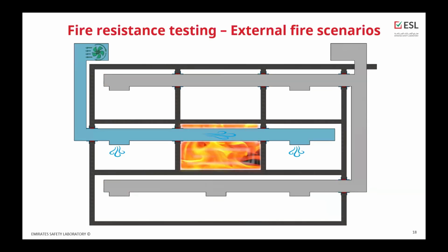The external fire scenario means that the duct is passing through a compartment where the fire occurred. This might be either a ventilation duct or a smoke duct as well. For smoke ducts, fire in other areas cannot be allowed to affect the efficiency of the smoke management system when they are already serving another compartment. This is why it is very important for the smoke duct as well, and why leakage classification is also very important, either to include in addition or to have in the classification code, because this provides provisions to eliminate or limit the spread of smoke through the building.